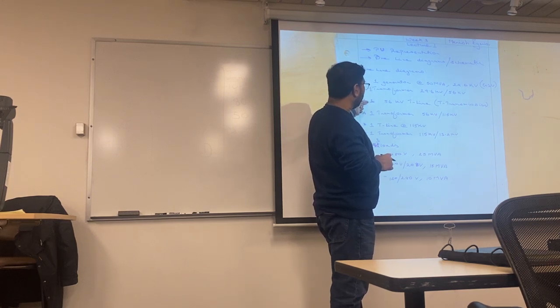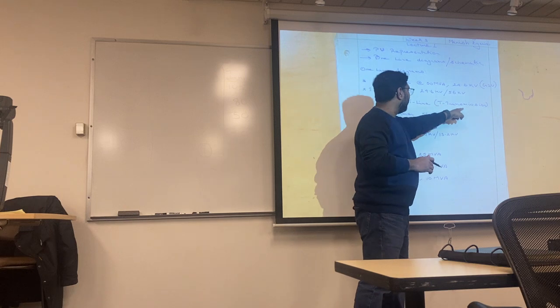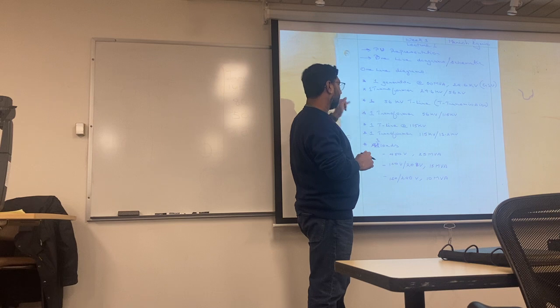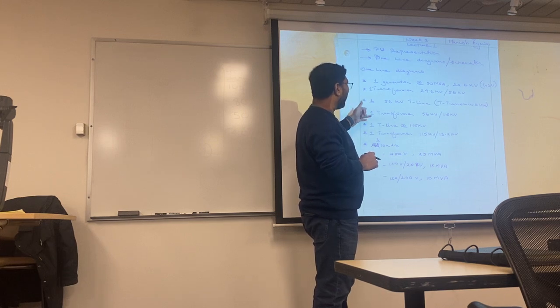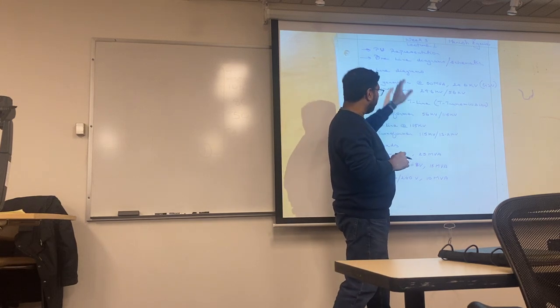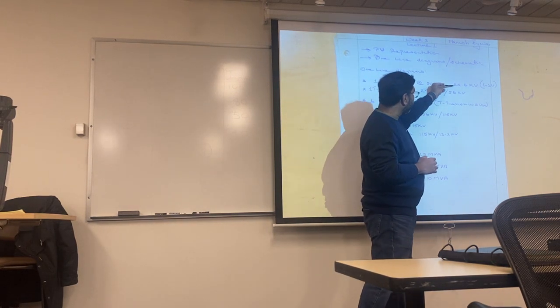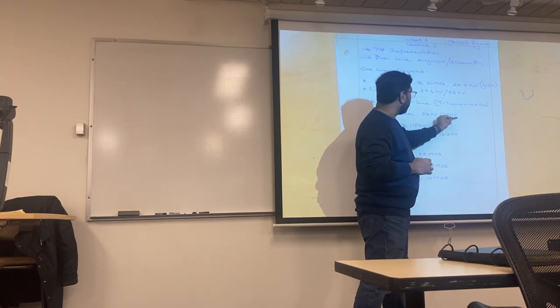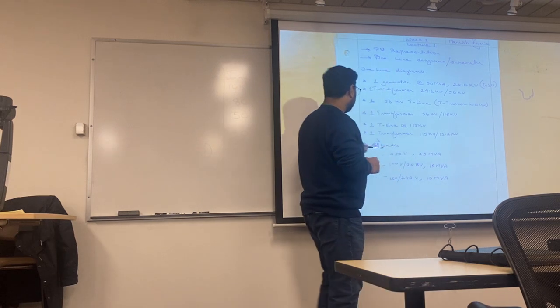Right after the transformer, there's a 56 kV T-line, T standing for transmission. Since it's transmitting over very long distances, sometimes several hundred miles, I want another transformer to step it up from 56 kV to 115 kV. So I produce 24 kV, step it up to 56, then step it up again to 115.